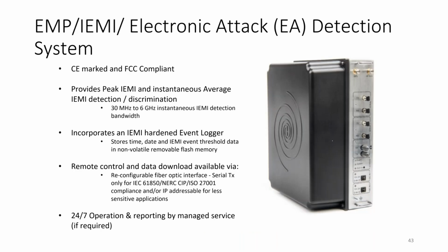So in addition to the mitigation of the radiated and coupled, we were also concerned about IEMI attacks that might be more focused on just disruption of data, where back at our control centers, our operators may see data that is incorrect due to some type of electromagnetic interference. So we installed also an IEMI detector that allows us to compare the signals that we're getting from the hardened enclosure to the signals that we're getting from our non-hardened substation infrastructure. We can do that comparison and then also monitor any magnitude and frequency of signals that we might be seeing to determine if some type of nefarious attack is underway.